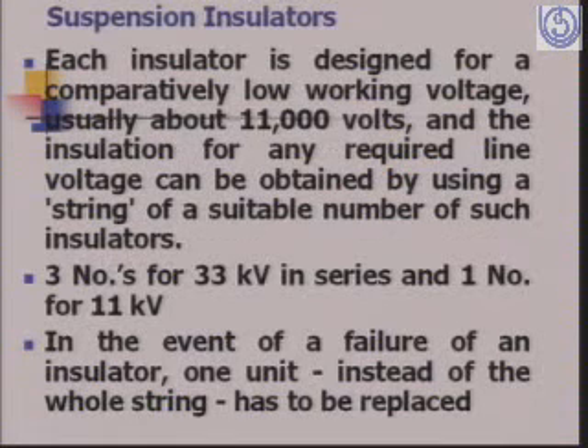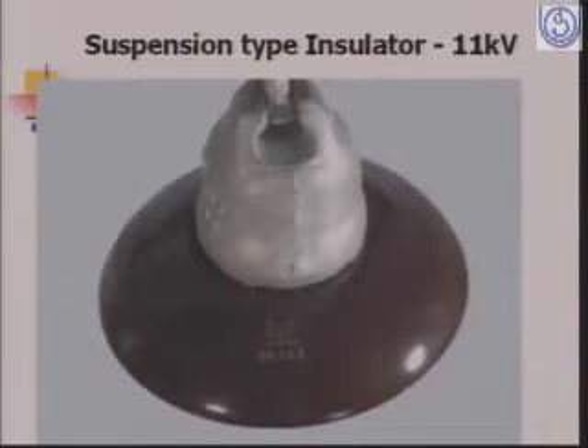Each insulator is designed for a comparatively low working voltage, usually about 11 kV, and the insulation for any required line voltage can be obtained by using a string of a suitable number of such insulators. 3 numbers for 33 kV in series and 1 number for 11 kV. So the 11 kV insulator will consist of 1 disc, and the 33 kV insulator will consist of 3 discs. In the event of a failure of an insulator, 1 unit instead of the whole string has to be replaced. Whereas in the case of the pin insulator, the entire pin insulator has to be replaced. So this is the advantage of a disc insulator. You can see this is an 11 kV disc insulator.